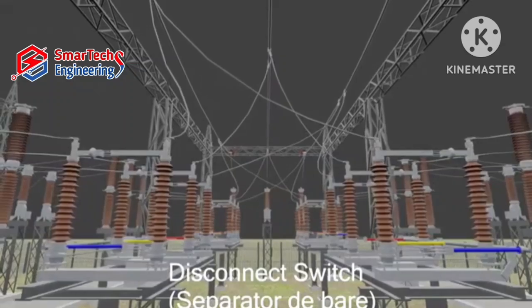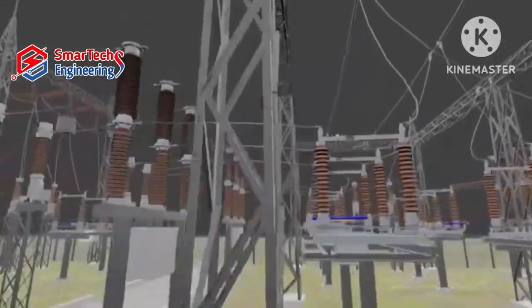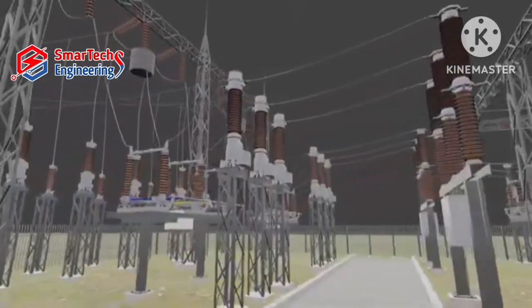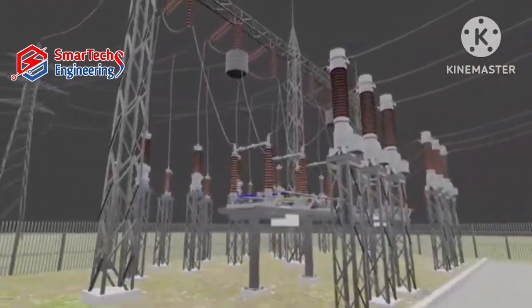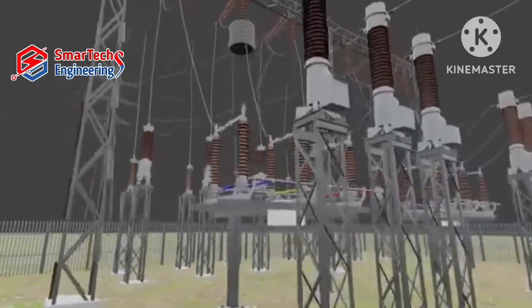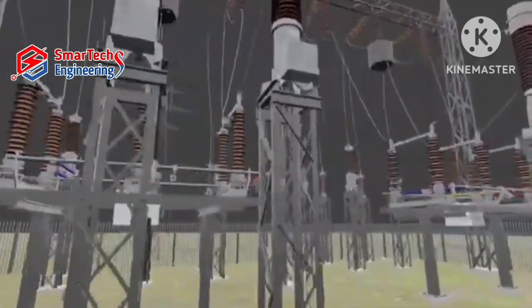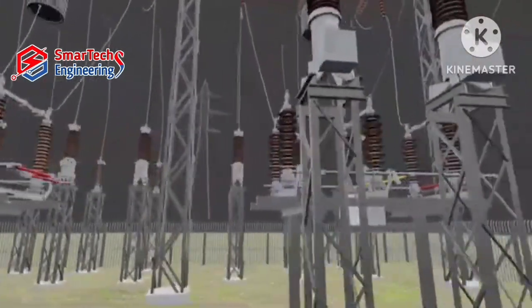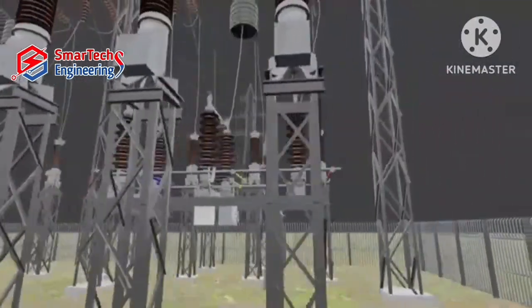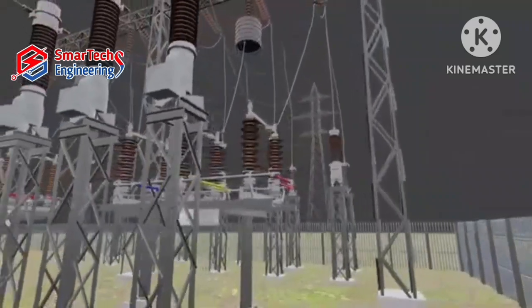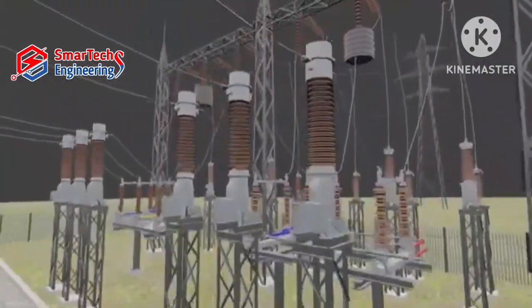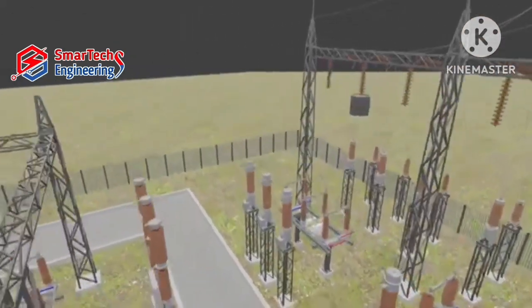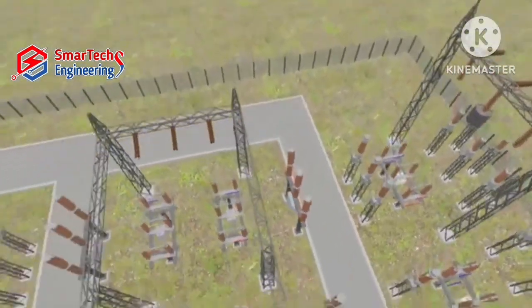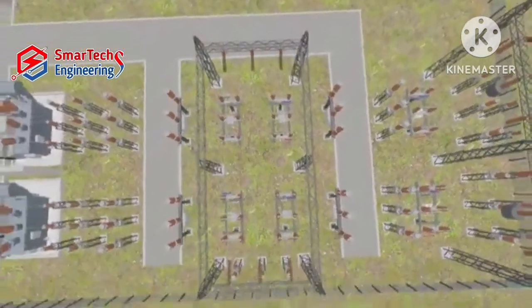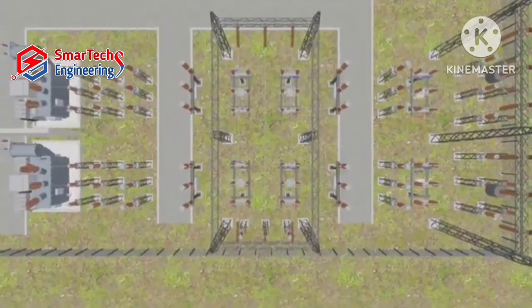A disconnector, or isolator, is a mechanical switching device used to isolate equipment. A disconnector switch only operates on no load condition. You can see here the disconnector switches for each line: red, yellow and blue. Here you can see the overview of the 110 by 20 kV substation.